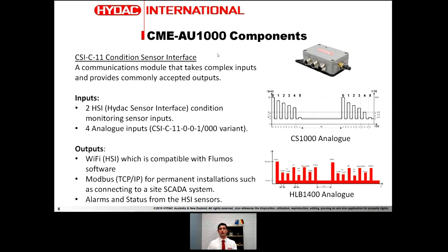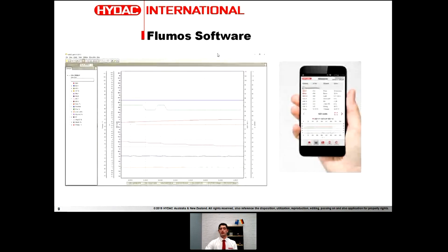Flumos is the mobile phone or mobile device app. On the left-hand side is Flumos Lite — a free software package from HYDAC that can talk to the CSIC11 and show you the values from your sensors, including trending ISO count, saturation levels, dielectric constant and conductivity. On the right-hand side is the mobile app. The idea is that on a mine site, there can be a permanent installation through the SCADA port going back to their computer systems, while a fitter can use their mobile device to access the CSIC11 and immediately see live sensor values on site.